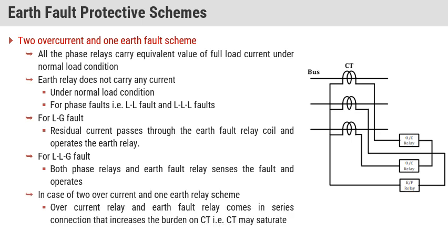In the two overcurrent and one earth fault scheme, the overcurrent relay and earth fault relay come in series connection, which increases the burden on the CT, and the CT may get saturated.